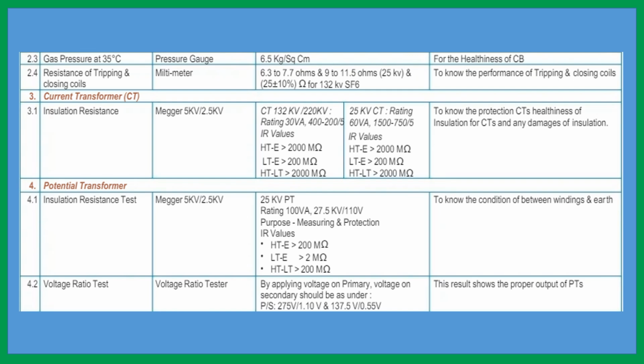SF6 circuit breaker resistance between the two contacts, movable contact and fixed contact, is 6.3 to 7.7 ohms and 9 to 11.5 ohms for the 25 kV LV side, and for the 132 kV side it is 25 plus or minus 10% ohm for the 132 kV SF6 circuit breaker. It is maintained. Okay. So possibly it is measured with a ductor meter.